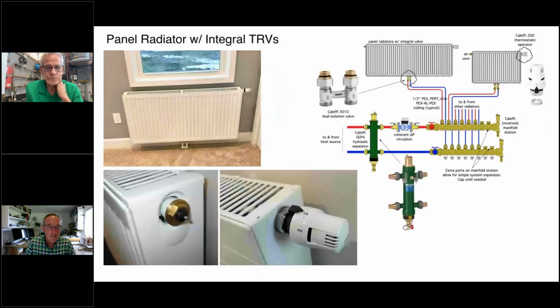Here's a quick example. This is another flavor of a thermostatic radiator valve, or TRV. Here we've got a panel radiator. This particular one is a Myson product. You'll see at the bottom here, supply and return tube. But up in the upper corner, you actually have a valve assembly built right into the radiator. So there's a core assembly that screws into the radiator, and here's that linear shaft, spring-loaded.